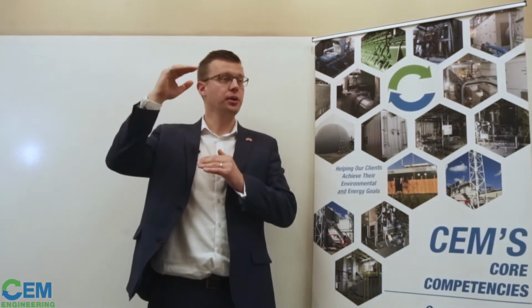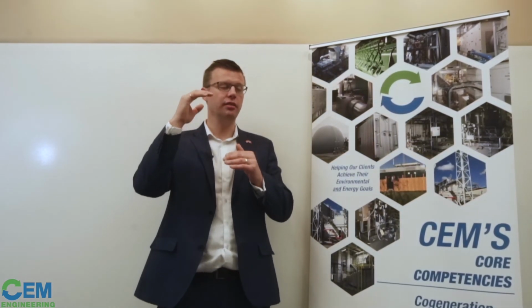As the spark spread gets bigger, the benefit of cogeneration financially continues to increase. And so if you have a traditional plant with the efficiencies we talked about earlier, you have electricity that you're consuming at about 14, 15 cents per kilowatt hour. When you cogenerate, because you're recovering the heat, you're doing it very efficiently, you can generate electricity for use at 3 or 4 or 5 cents. So for every kilowatt hour your plant consumes, you're saving anywhere between 8 and 10 cents, which over the course of a year for a big plant is significant savings, in the millions of dollars range for a system of 3 to 5 megawatts. So it's a significant savings opportunity for anybody who does cogen.